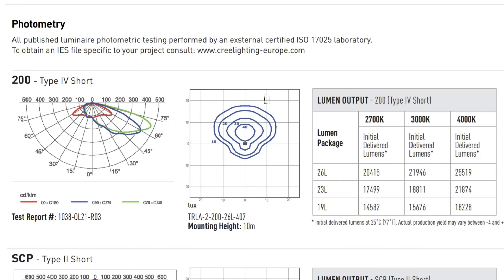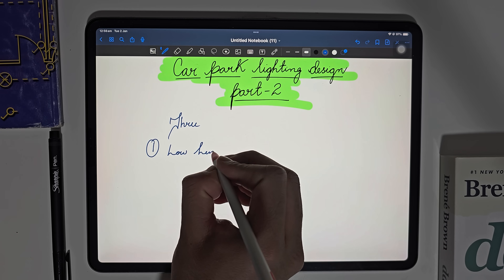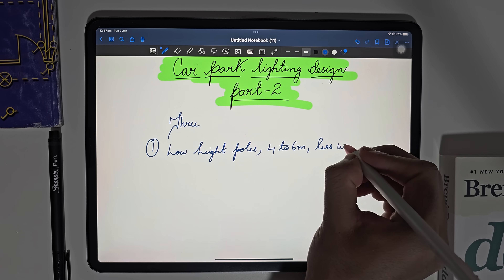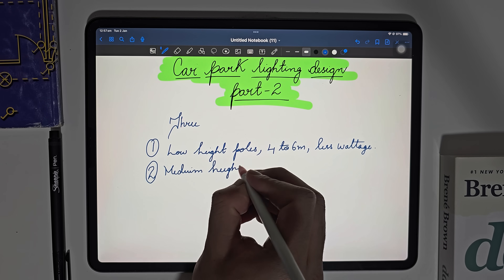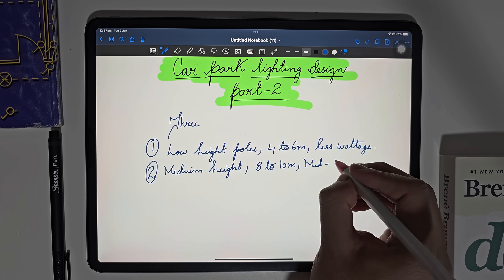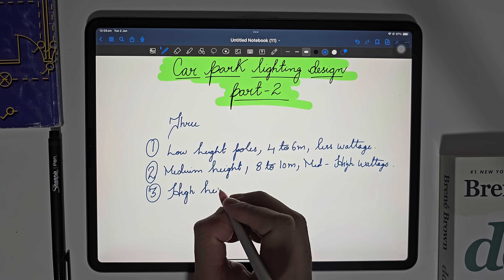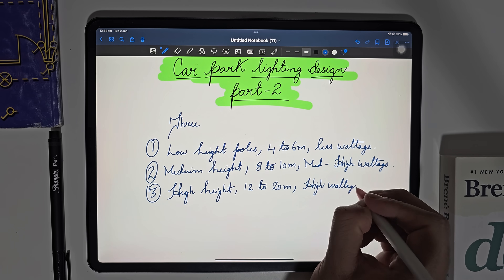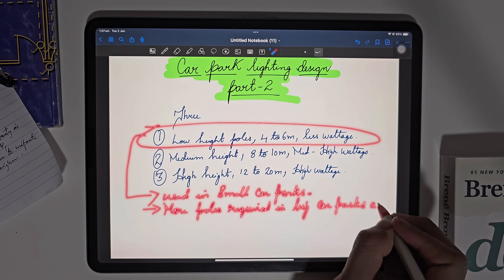When mounted at 10 meter height, it gives us a minimum of 15 lux for up to 20 meters at the front and up to 15 meters on each side. There are three types of pole height for mounting light fittings. The first one is a low height pole with pole height from 4 to 6 meters, and basically light fittings with less wattage are used in this one. The second one is a medium height pole and it varies from 8 to 10 meters, and medium to high wattage light fittings are used.